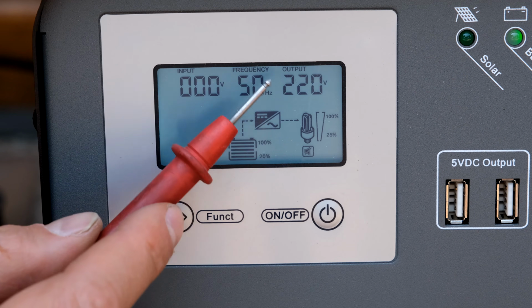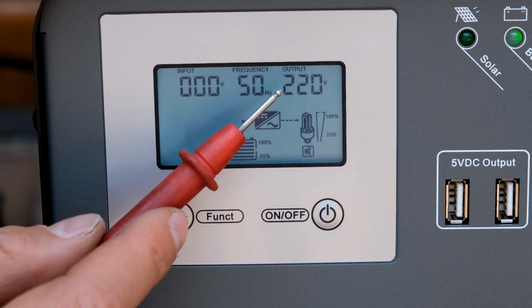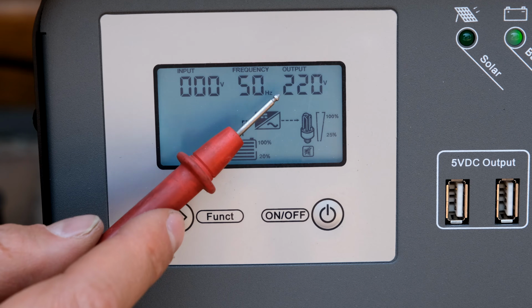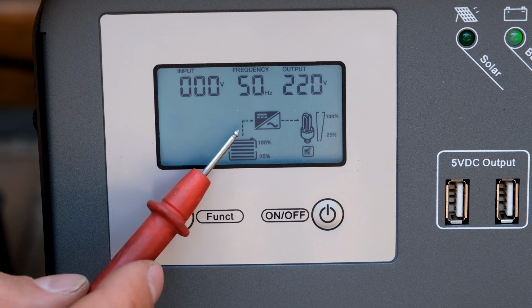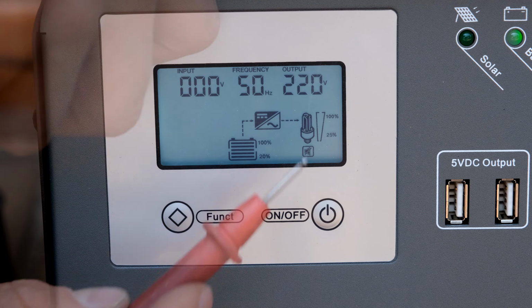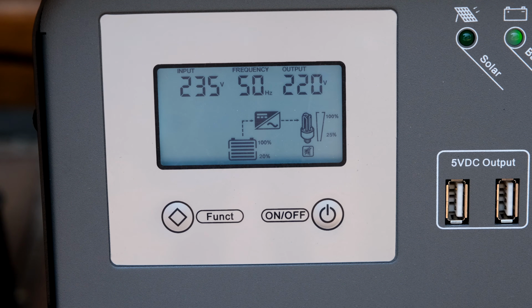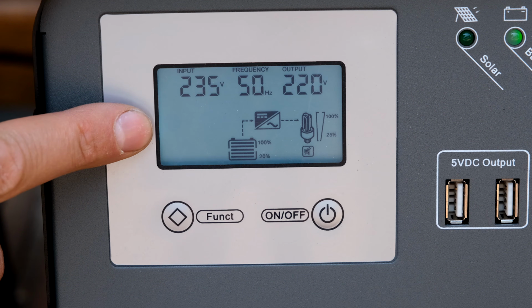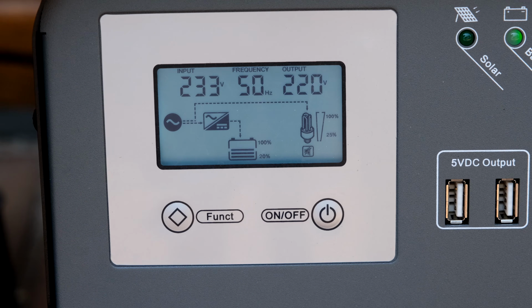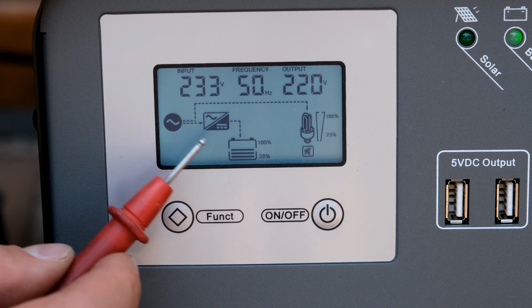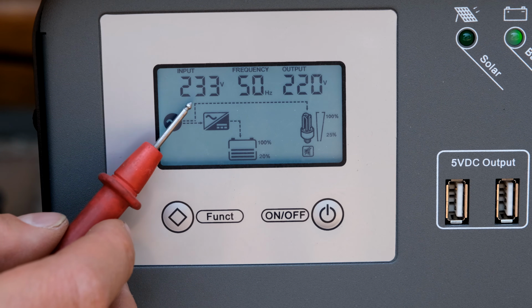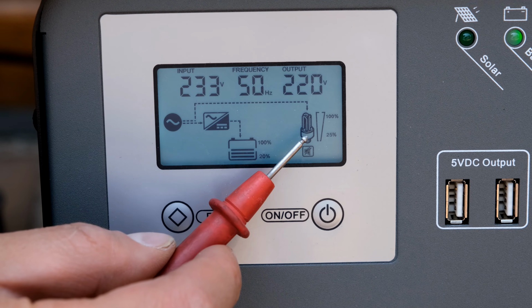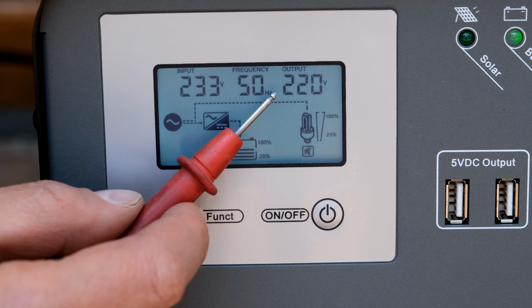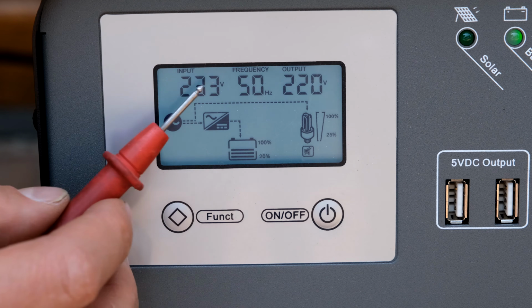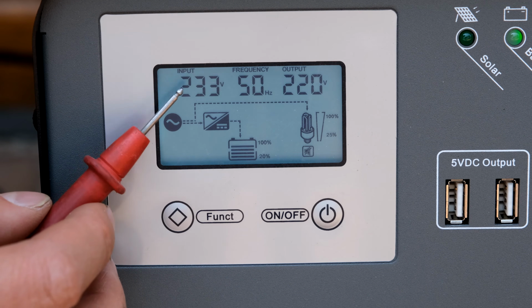But notice that now, only when the mains is unplugged do I get that 220 volts, and notice the dotted line goes like that. When I return, the mains is now plugged back in. Notice that it is now back in charging mode, and the mains is now supplying the output. So even though it says the output is 220, it's not - the output is what the input is, which is 233. This is a little bit misleading.